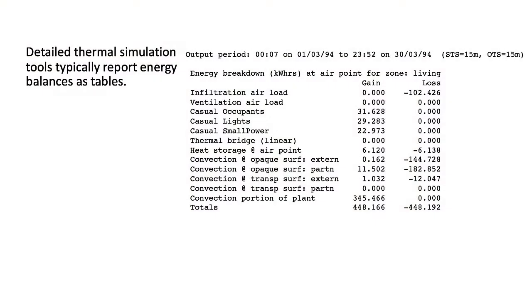Let's move from a sketch representation to what we might actually see in an engineering tool. Here's a zone energy balance from a detailed numerical simulation model for an assessment run during the month of March. Each line of this report tracks the gain and loss over that period for a specific heat flow path. We can see in the totals line that gains and losses are almost identical.